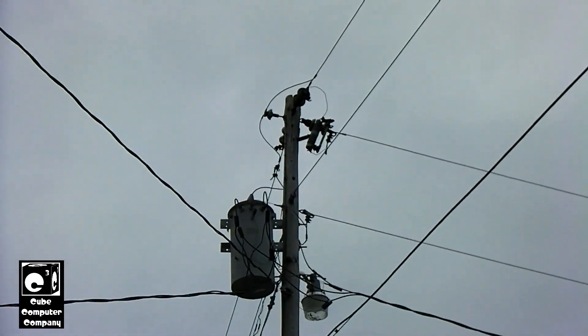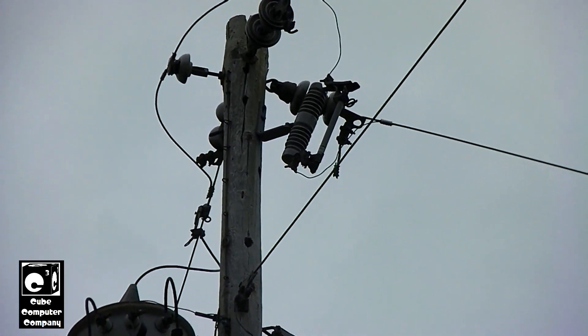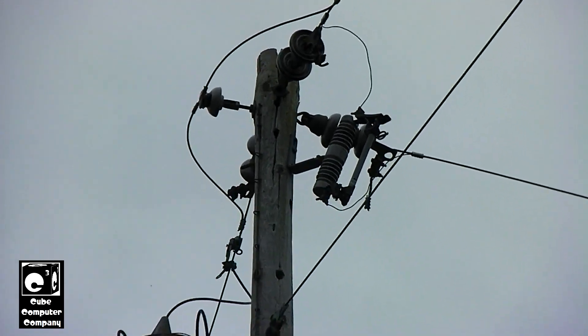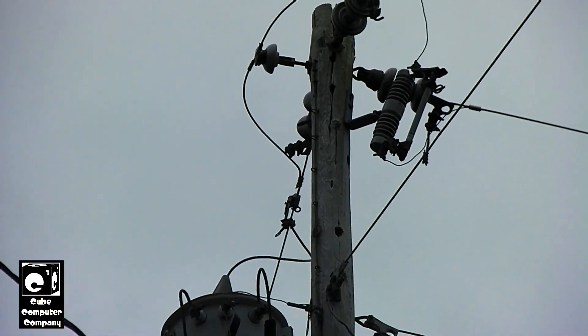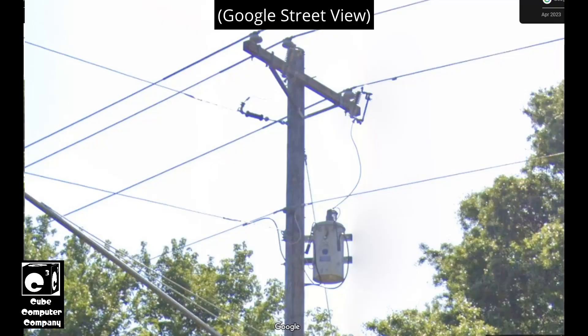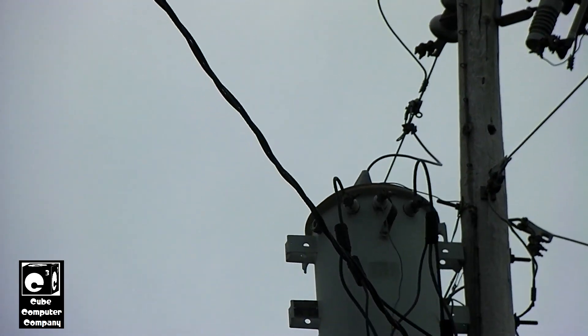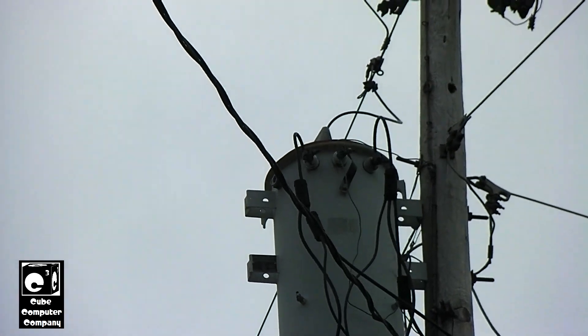Right up there is the fuse cutout I was talking about — that's what went kapow in the previous video. A lot of times when these fuses let go, people think transformers explode; it's just a common myth. On some distribution systems, Energy United is starting to put fuse cutouts on the main line transformers. Whereas on sidelines, the primary cable going from the top of the transformer is still connected directly to the phase with no external fuse. The transformer, being a CSP transformer, has a fuse internally.